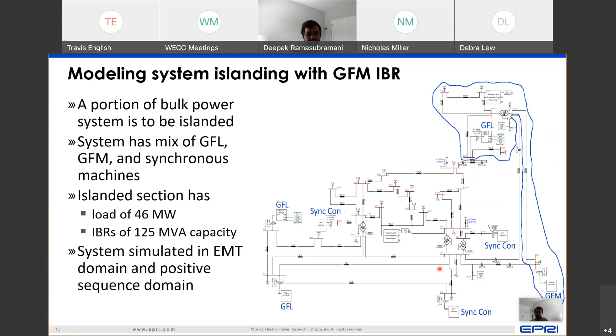And now we simulate this both in the EMT domain and the positive sequence domain. This is what you see with respect to the frequency response. The frequency in the main part of the system, this is the EMT result, upon the islanding that occurred, increases because there's an overgeneration in that region. The frequency drops in the island with the grid forming inverter and it settles down. And you see a similar trend of response in the positive sequence domain.